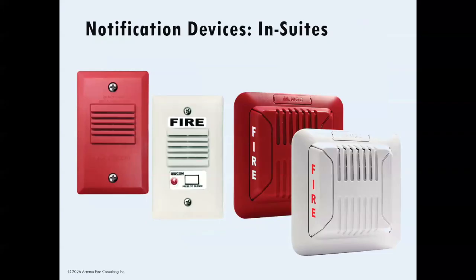When we start talking about in-suite devices, the building code has for many years now required that all suites must achieve a minimum decibel reading of 75 decibels over ambient sound in the bedrooms and 65 decibels in all other areas. With the code update in 2024, it also became a requirement that all bedrooms must have low frequency horns, which are easier for people to hear and more likely to wake them up at night. In order to fulfill the code requirements, we install notification devices in the main living area, as well as in each bedroom to ensure that the decibel levels can be achieved.